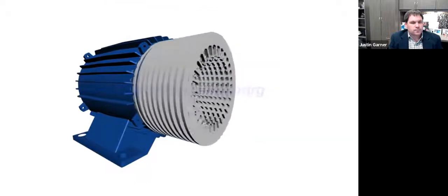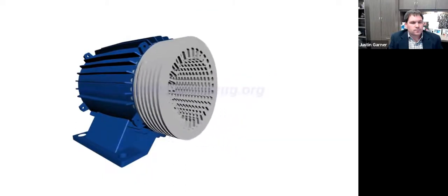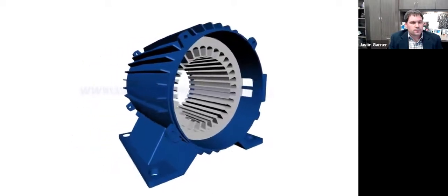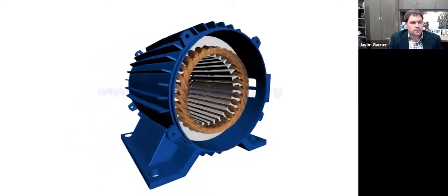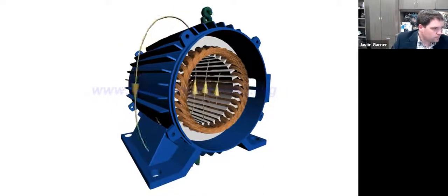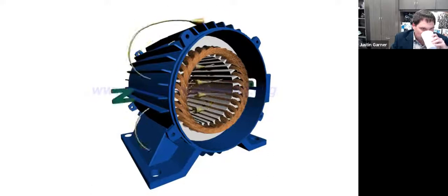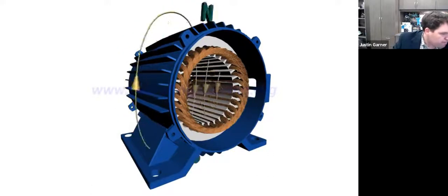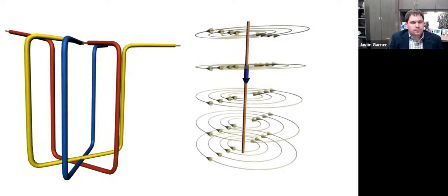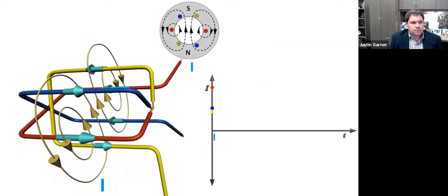Stator is made by stacking thin-slotted, highly permeable steel laminations inside a steel or cast iron frame. Winding passes through slots of stator. When a three-phase AC current passes through it, something very interesting happens. It produces a rotating magnetic field. To understand this phenomenon much better, consider a simplified three-phase winding with just three coils. A wire carrying current produces magnetic field around it. Now, for this special arrangement, magnetic field produced by three-phase AC current will be as shown at a particular instant.